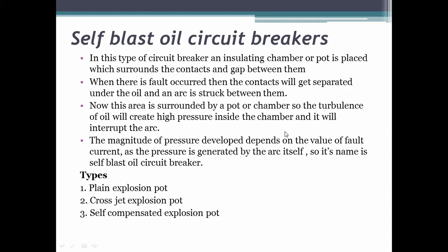Some turbulence will be there, and it will create high pressure inside the chamber, and it will interrupt the arc. When the arc is created, that heat is extracted by that oil.